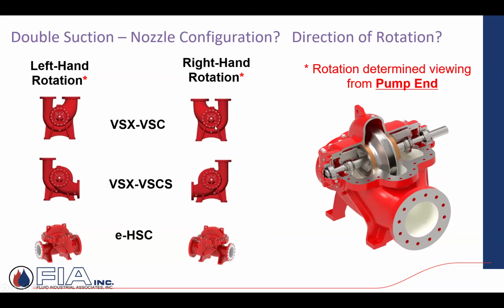Only because if you think about it from a floor space standpoint in that mechanical room, your piping is up high, coming down, dropping right into that casing. These other two down here in the middle and on the left, which sometimes they might have to because of the orientation, this VSCS, this side inlet, this side horizontal inlet, it might be the application more like a cooling tower, and the piping is down low. And we're going to enter right into that side. That'd be an application for that VSCS.